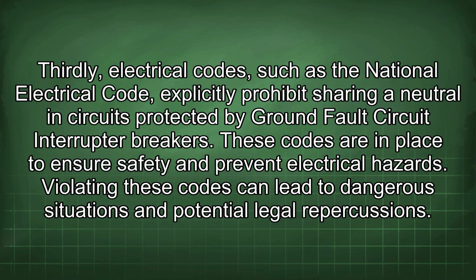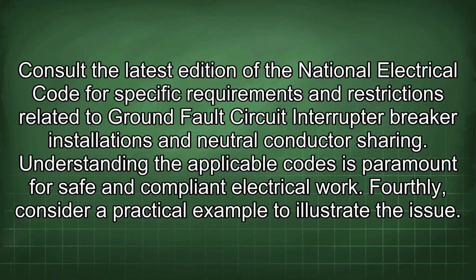Thirdly, electrical codes such as the National Electrical Code explicitly prohibit sharing a neutral in circuits protected by ground fault circuit interrupter breakers. These codes are in place to ensure safety and prevent electrical hazards. Violating these codes can lead to dangerous situations and potential legal repercussions. Consult the latest edition of the National Electrical Code for specific requirements and restrictions related to ground fault circuit interrupter breaker installations and neutral conductor sharing. Understanding the applicable codes is paramount for safe and compliant electrical work.